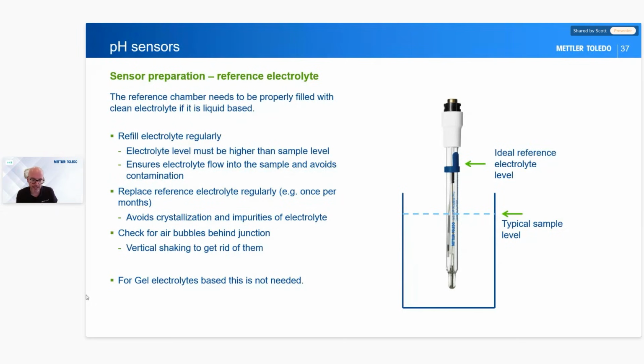So we always empty and clean it. We should do this regularly, about once a month. So once a month, we should empty that electrolyte out and refill it again. A little plastic pipette is one of the best ideas, and you can turn the electrode upside down and just suck it out of the little hole that's there and then replace it again. If we get any crystals in there, then we should refresh with fresh solution, dissolve the crystals, and empty and refill again. Because obviously we want to keep that same constant concentration. If we dissolve crystals in there, that's going to change the concentration. So dissolve the crystals, empty it and replace it again.